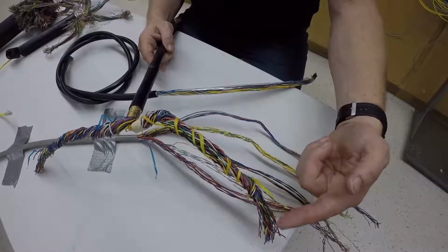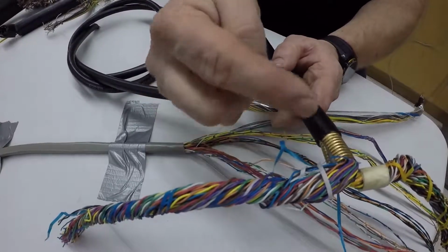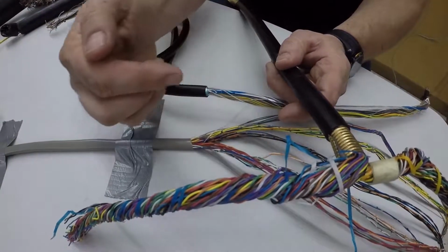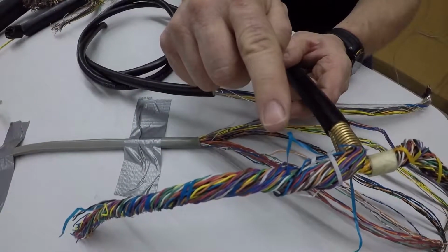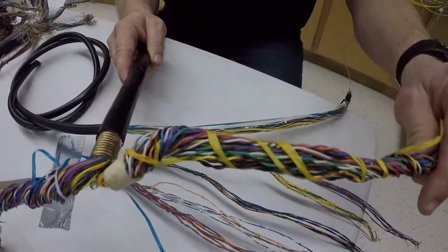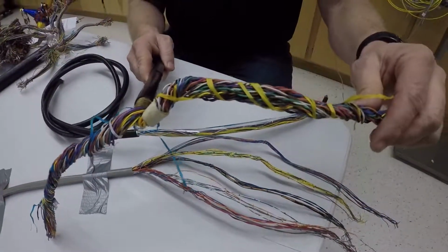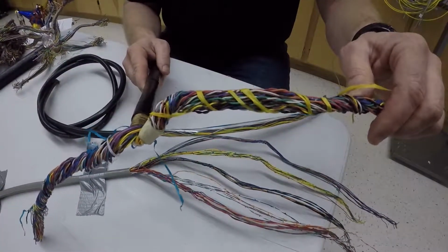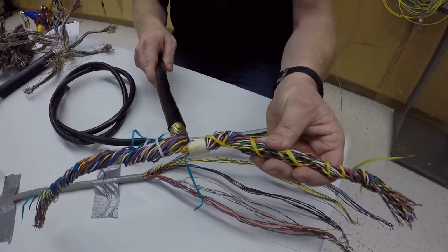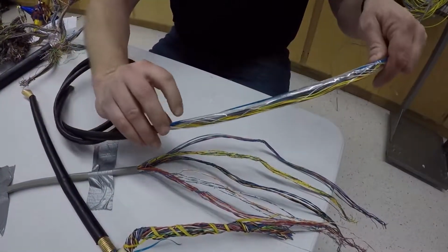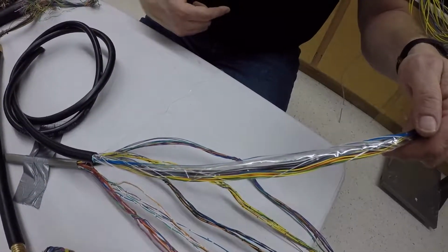Well, the color codes are all the same. How do you identify that? Well, they're identified with this ribbon, and it's called a binder. The first 25 binder is wrapped in a blue binder group. Then we go to the second 25 pair, same color code as in here, but it's wrapped in an orange binder group, and that's how we identify the different binder groups. So if you have, this is just a 50 pair cable, here's a 25 pair, and you can see that little blue binder wrapping all 25 pairs.